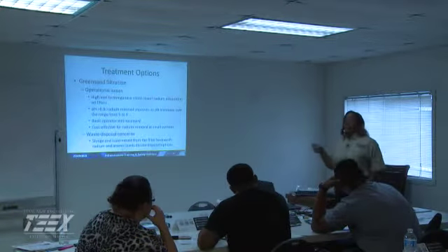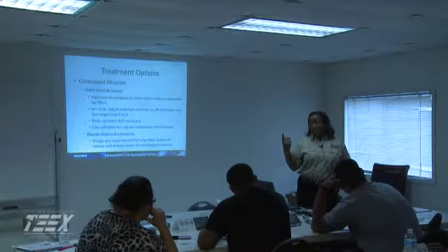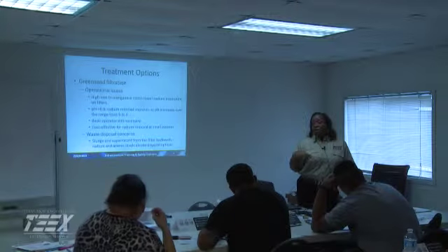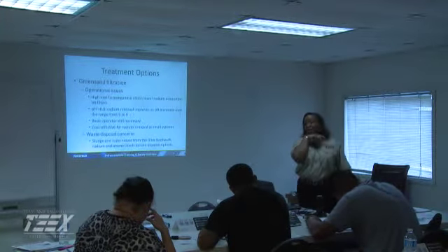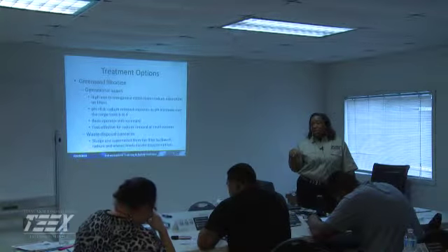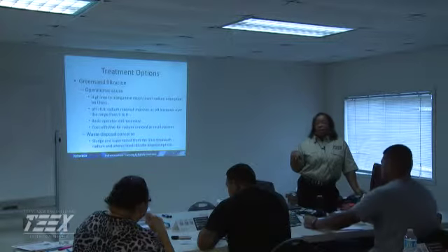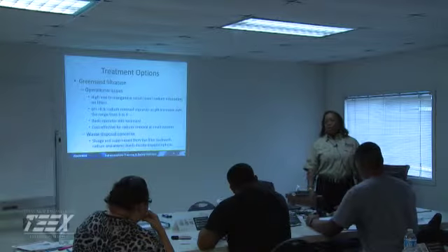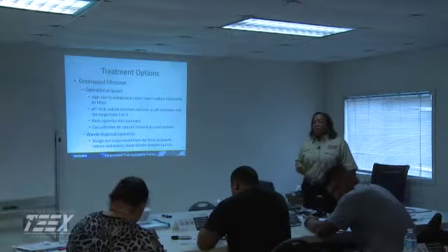If it's accurate, then I'm going to start looking at other things going on in that water. I may even look at the alkalinity to see what type of alkalinity I have, and does that make sense? Based on whether it's a hydroxyl alkalinity, or the total alkalinity or carbonate alkalinity, it's going to give me some indication of whether or not that's a true pH value. Was this a one-time deal that it spiked like that? At one of our plants, I thought that the pH was high, and I didn't know if it was the source water. Okay. Usually source water is not that high unless they're being dumped on, which is always a possibility if it's a surface water source. But with a groundwater source, if it's not typically where it runs, start with that meter and then look at the alkalinity to verify the numbers.